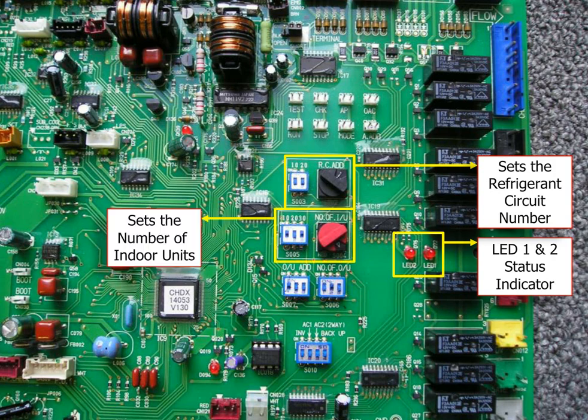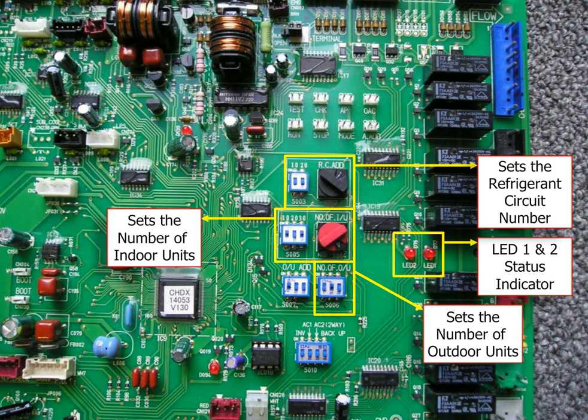The red dial labeled S004 sets the number of indoor units that are connected to this outdoor unit or units. When multiple condensers are combined together, S006 is set on the main unit. This tells the main PCB that there are 2 or 3 condensers combined. The other setting that needs to be configured when condensers are combined is S007. This sets the outdoor unit address, and it tells the unit to either be the main or sub. An outdoor unit address of 1 sets the unit as the main. The main unit always has terminals 1 and 2 connected to the indoor units.